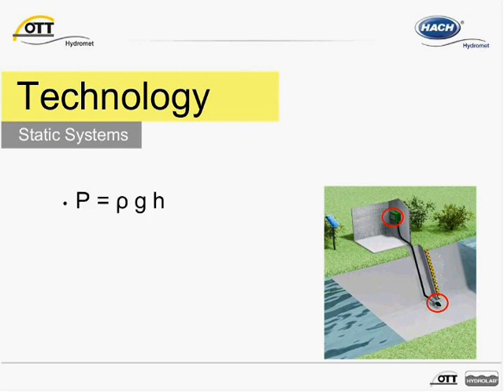Depending on the water level, shown here as H, above the orifice opening, an air pressure equal to the hydrostatic pressure, shown here as capital P, is established inside the measuring tube. In this equation, small g is gravitational acceleration and lowercase p is the specific gravity of water.